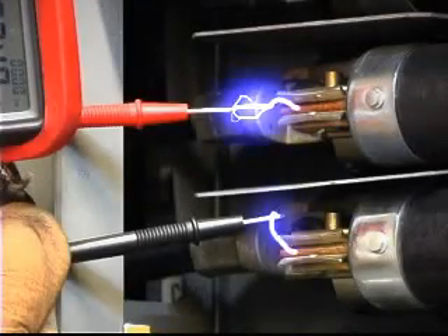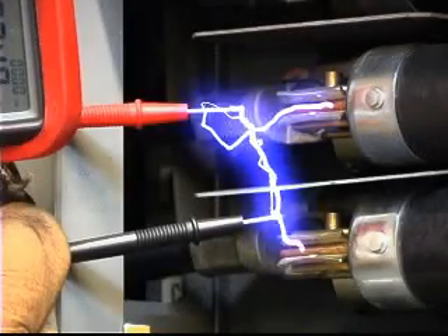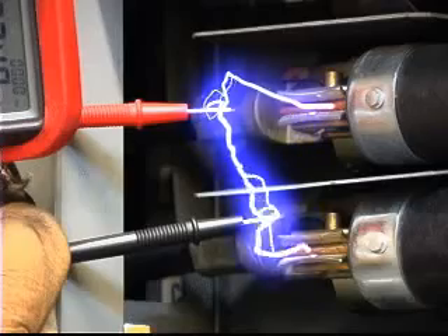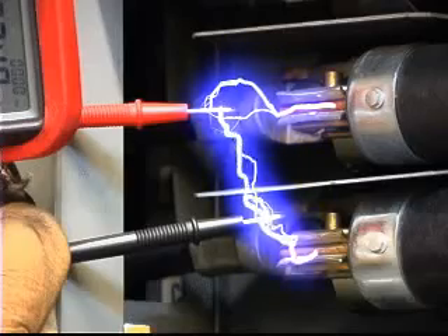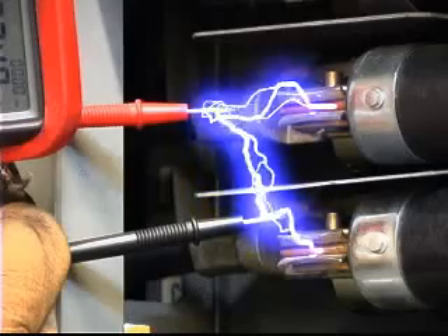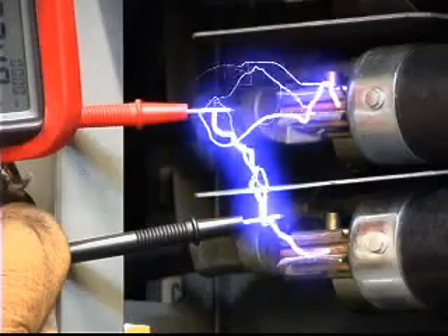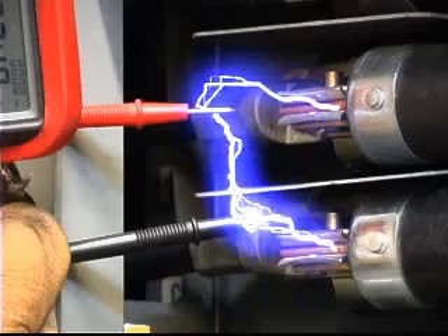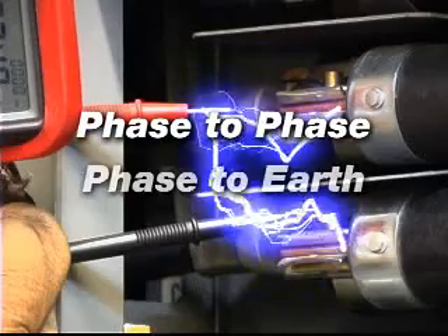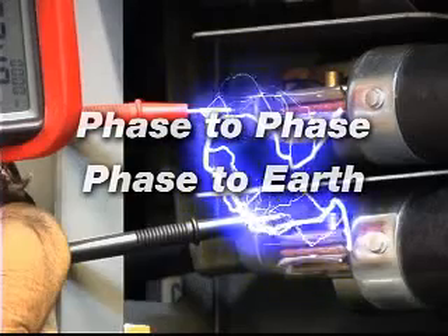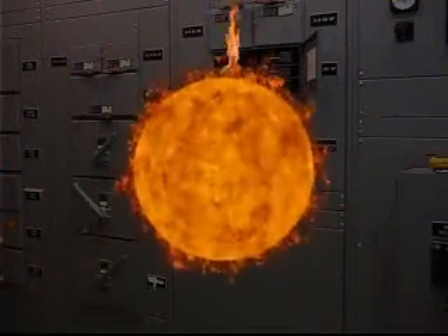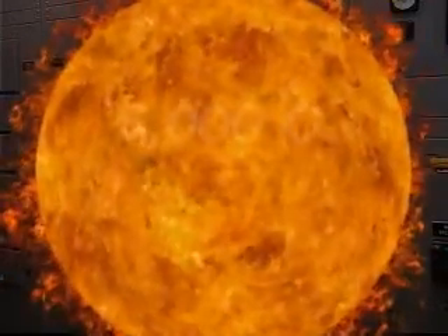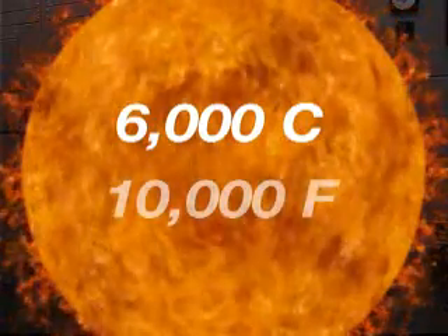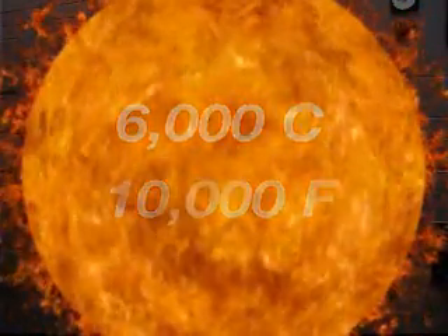If these two arcs join through close proximity of exposed metal from the test probes or other mechanisms, one large arc is formed, providing a low impedance path directly from one electrical phase to another. When two arcs join, they cause either a phase-to-phase or phase-to-earth fault. The result is an arc blast, which can lead to a plasma fireball fueled by the energy in the electrical system. When this occurs, temperatures can reach about 6,000 degrees Celsius or 10,000 degrees Fahrenheit.